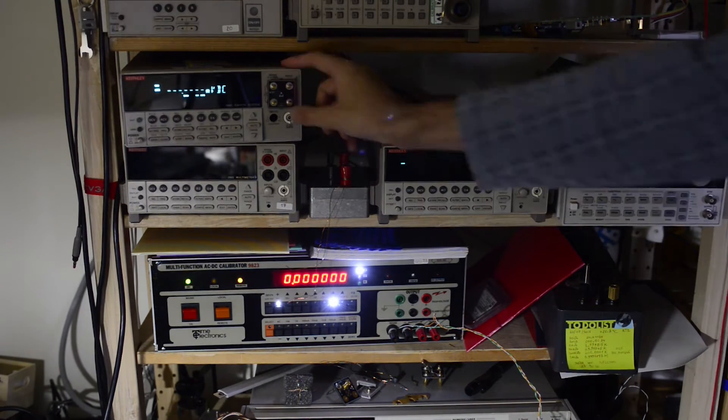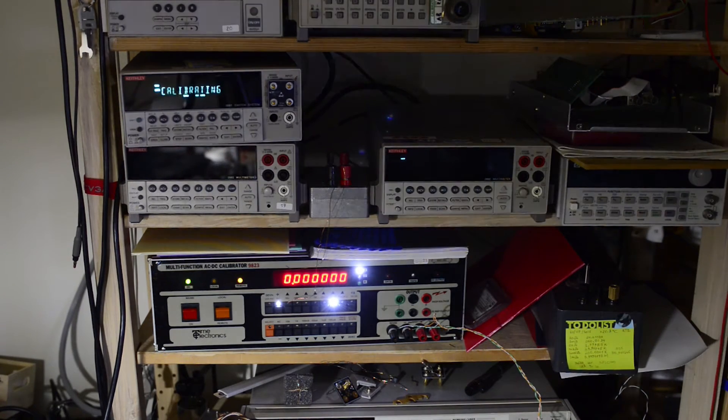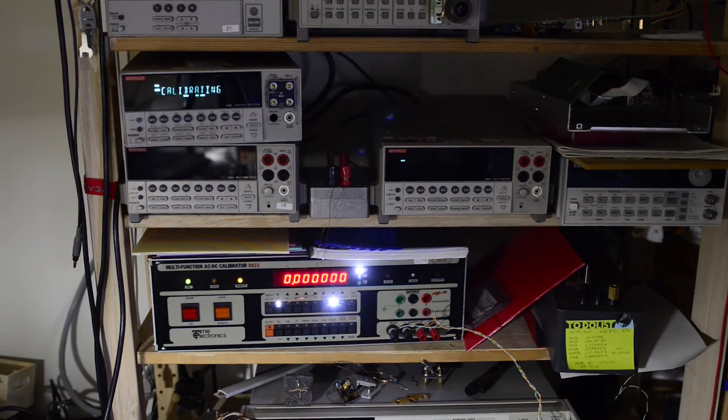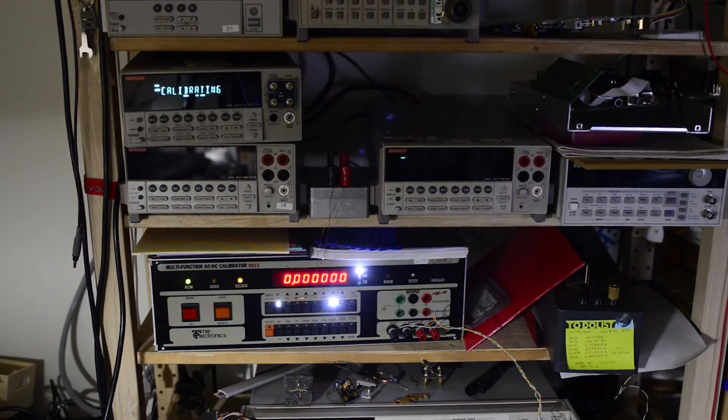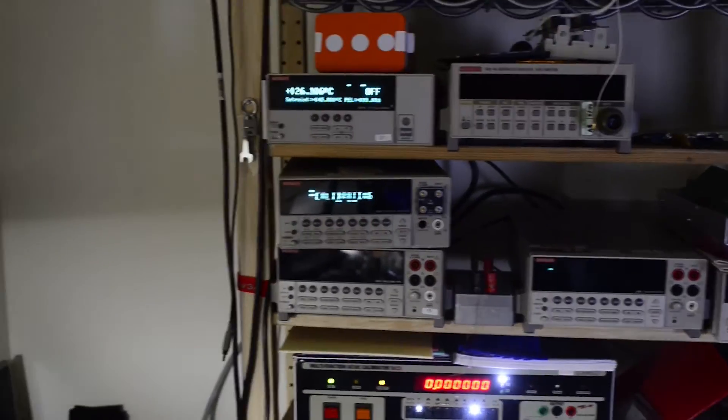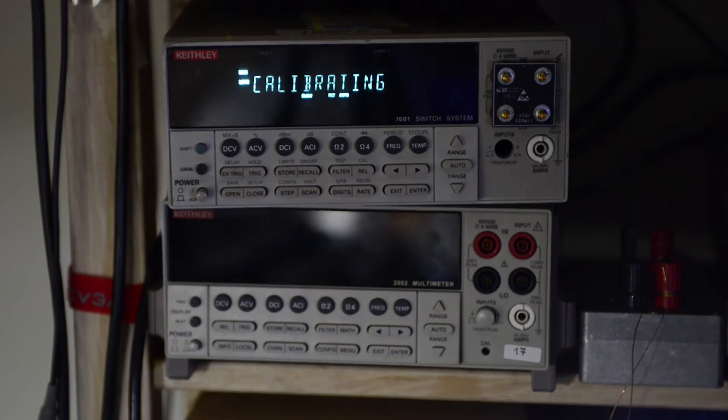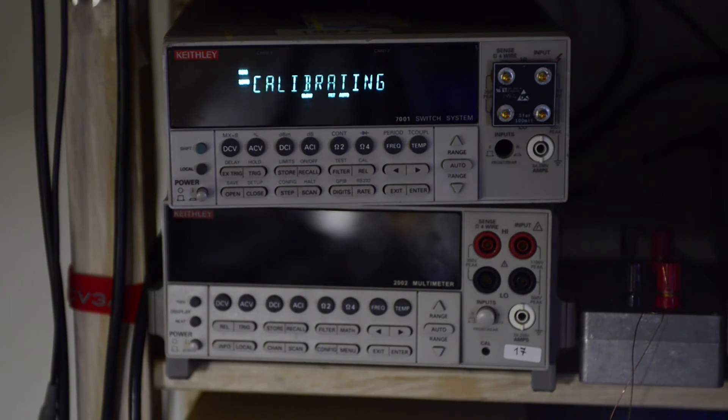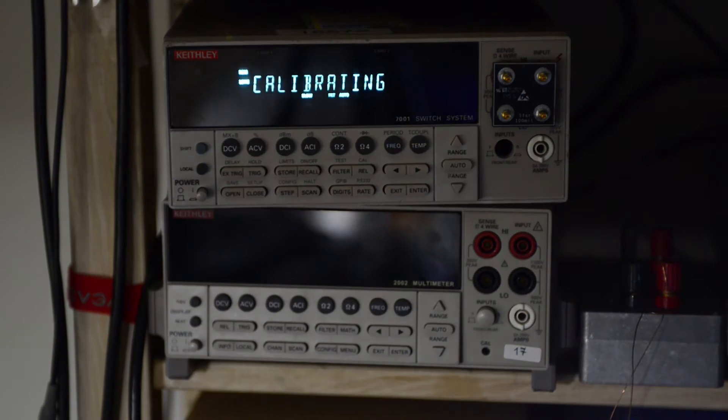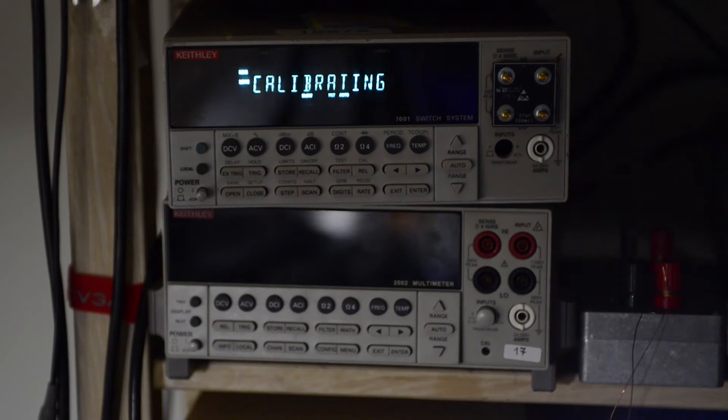Now it's time to start the calibration procedure. The first step is calibration with the short. It takes a few minutes, so be patient and don't touch the meter during the calibration procedure.